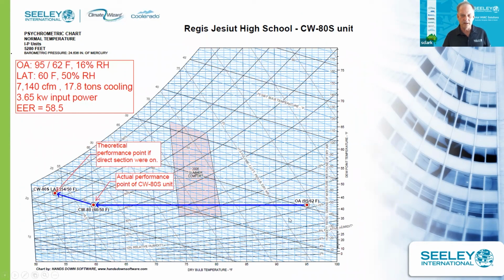If we look at that on the psychrometric chart, this is how it plots out. So we have a 95-62. We're doing sensible cooling. We're 2 degrees below the wet bulb. And this is based on actual site conditions, which typically are better than what we calculate in our spreadsheets. And then that unit had a direct evaporative pad that adds, we wanted a little more cushion for this gymnasium. And quite frankly, 60-degree air was plenty cold for their gymnasium. So to my knowledge, they haven't even turned this on. They could turn it on if they want a little bit of moisture for their gym floor and lower temperatures. So they could do that.